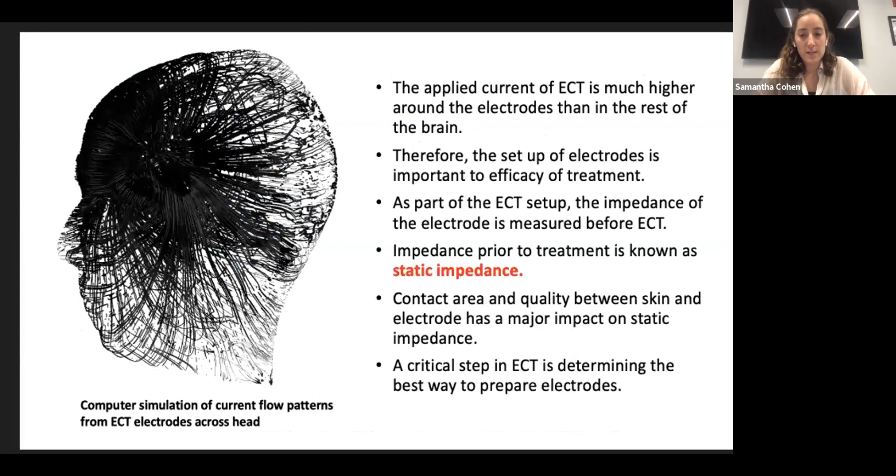During the administration of ECT, current density is much greater in the area surrounding the electrodes than in the rest of the brain. This is because current is entering the body via the electrodes. During the setup of ECT, the impedance of the electrode is measured with currents much smaller than those of the treatment. Impedance prior to treatment is called static impedance. Both the contact area and the quality of the skin electrode interface influence static impedance. As such, they are important in the setup of treatment.